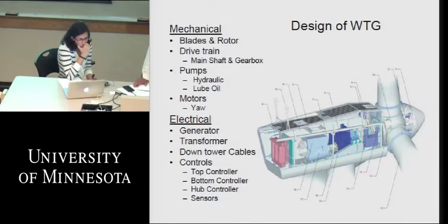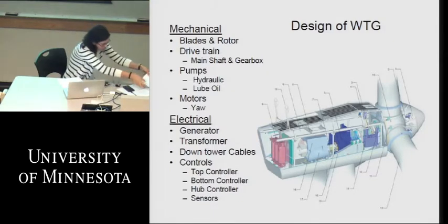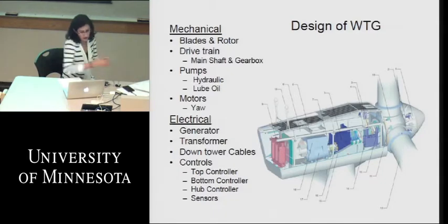On the electrical side, of course, the heart of the beast is the generator. What we're trying to do is create electrical energy, converting the kinetic energy from the wind into the mechanical system, and converting it to electrical energy to be delivered through the transmission system, and ultimately out into our load centers, which are major cities and power pools. The generator is a low voltage generator, meaning it's usually less than 1,000 volts. That is certainly the standard today. So we need a supplemental transformer to bring that voltage up from maybe 480 volts or 600 volts or 690 volts or even 1,000 volts to an acceptable medium voltage that a distribution company would generally operate at, like 13 kV or 25 kV.